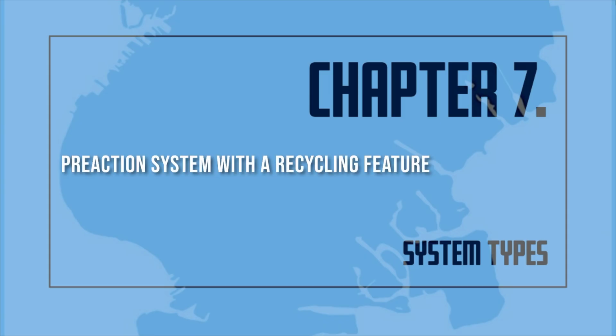Pre-action system with a recycling feature. A special kind of pre-action system is a recycling system for controlling sprinklers. This system shuts off the water when the fire has been put out or the heat drops. If the fire rekindles or the heat rises sharply, water is discharged again. The system continues cycling on and off as long as the fire persists.